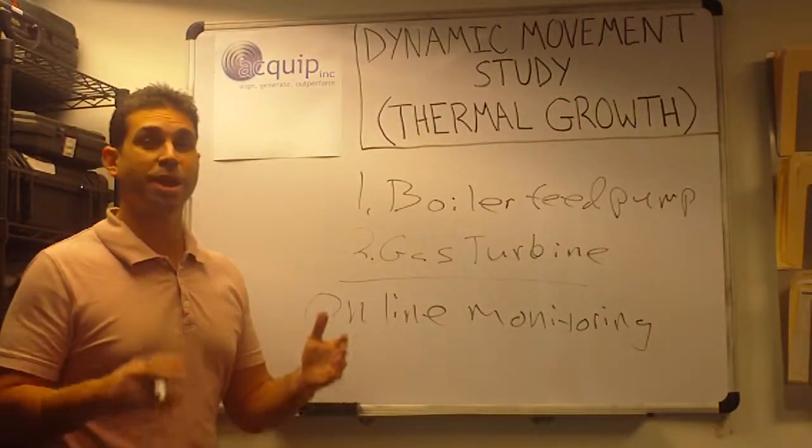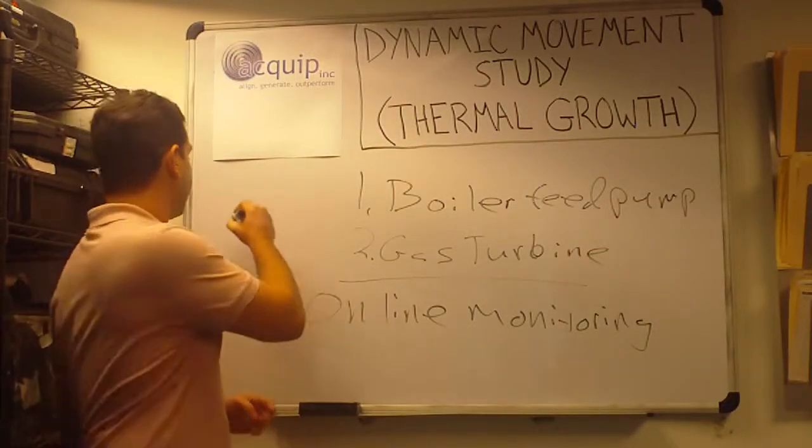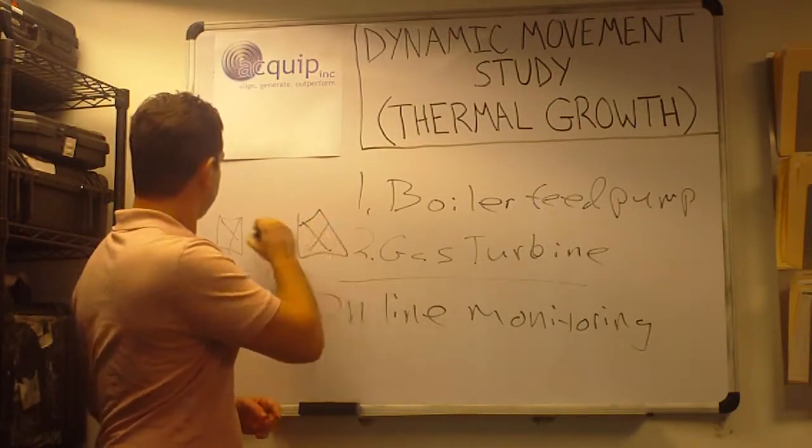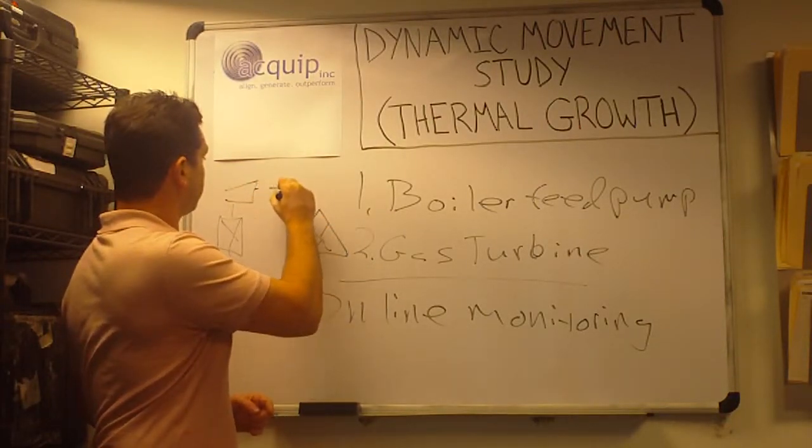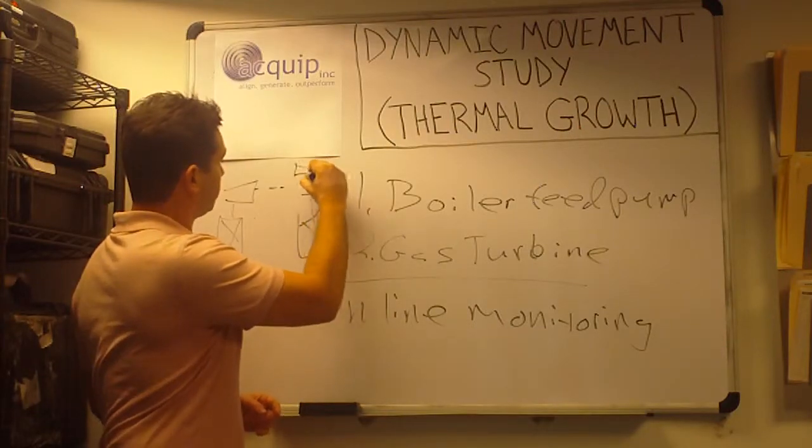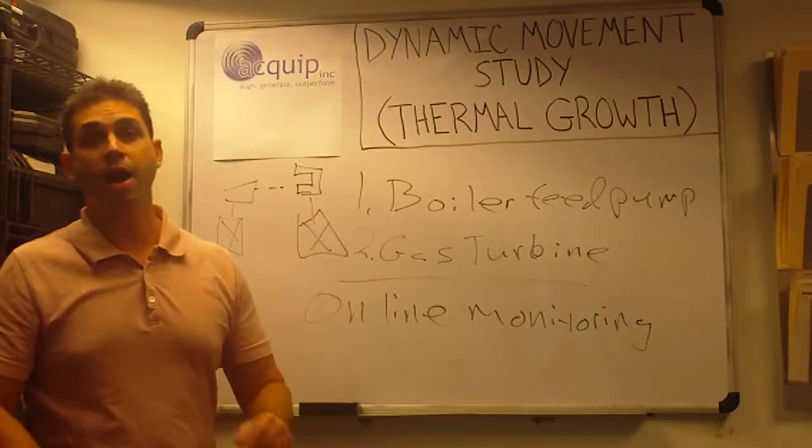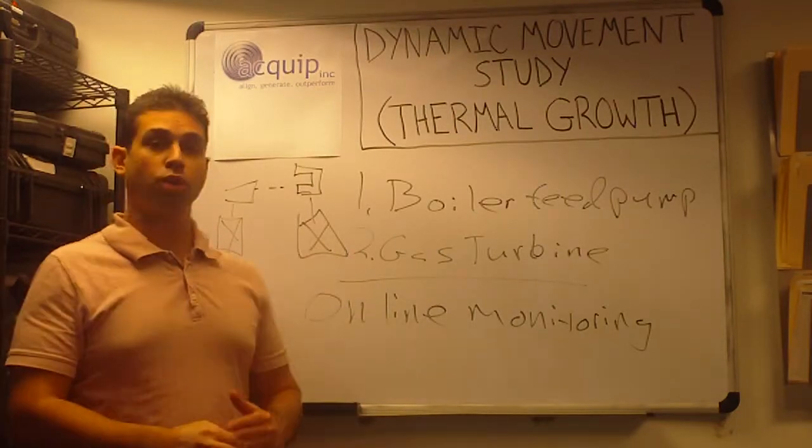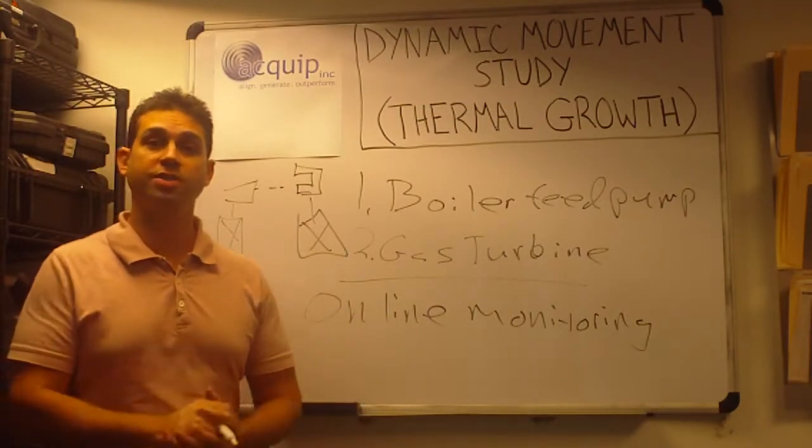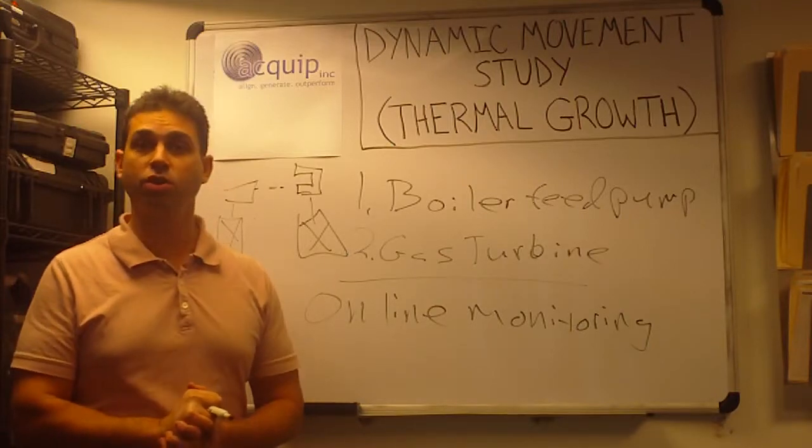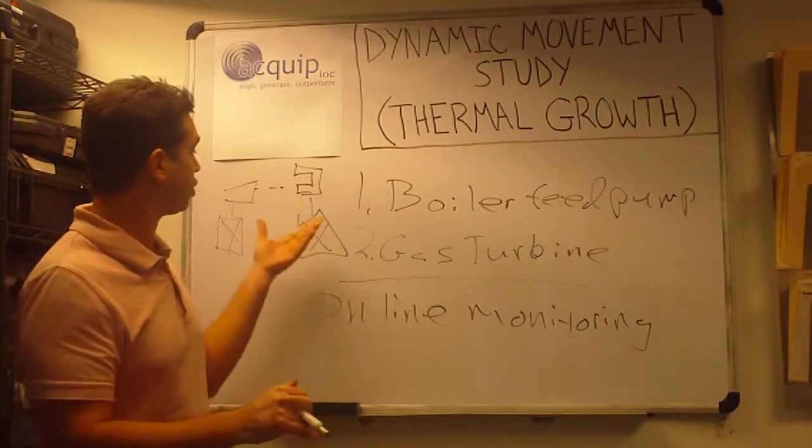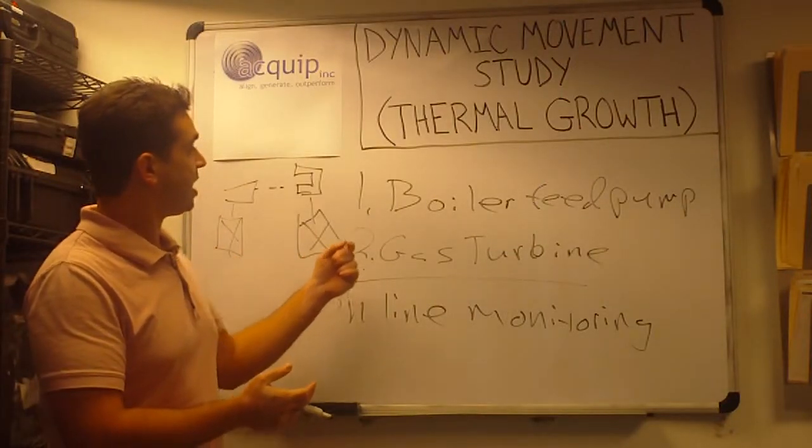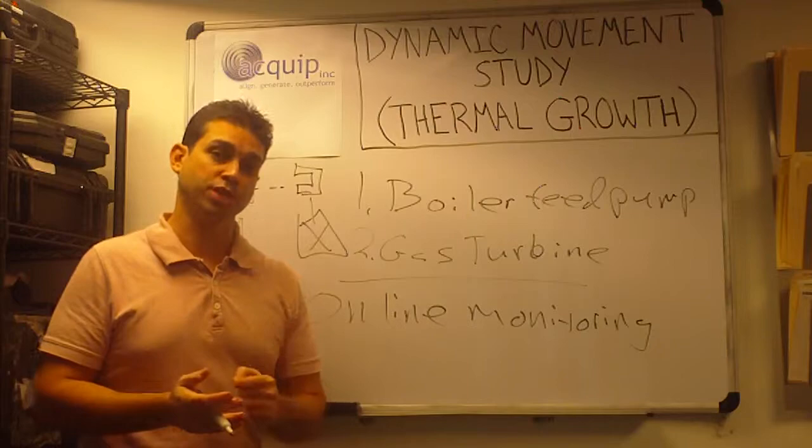The way that we do this is by actually hooking up a laser and a target to monitor the movement of your machine. By doing this, we're able to get the horizontal offset, horizontal angle, vertical offset, and vertical angle that happens across the coupling of your machine. We can do this at each one of the elements of your machine.